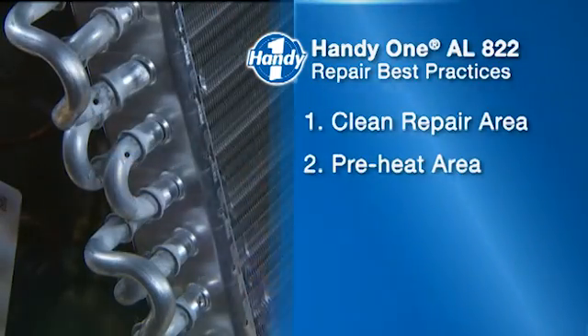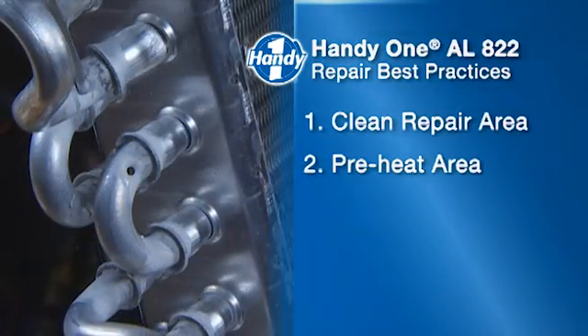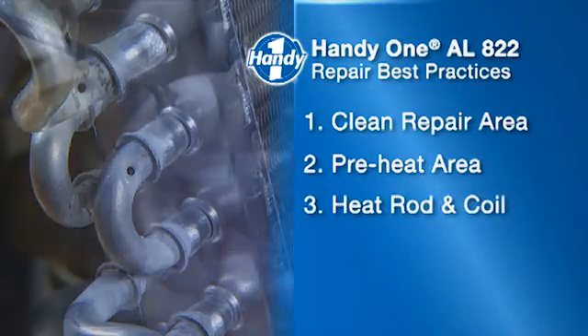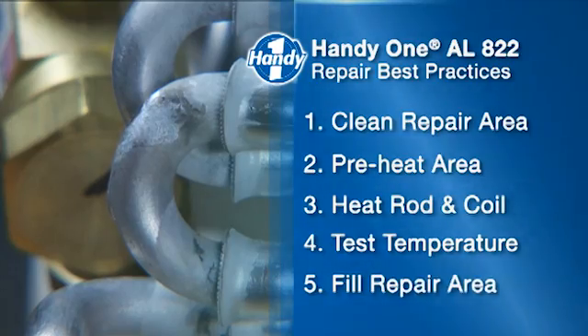Slightly preheat the area to be repaired. Then apply heat to both the rod and the coil. Once the flux begins to flow and the rod melts, fill the repair area.